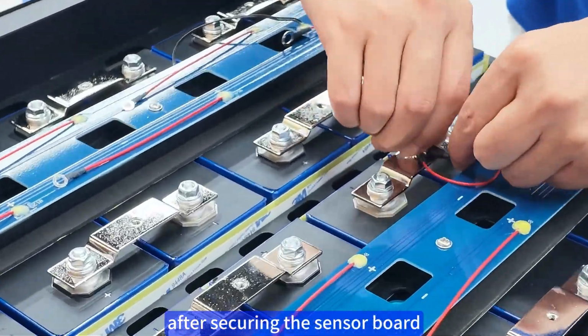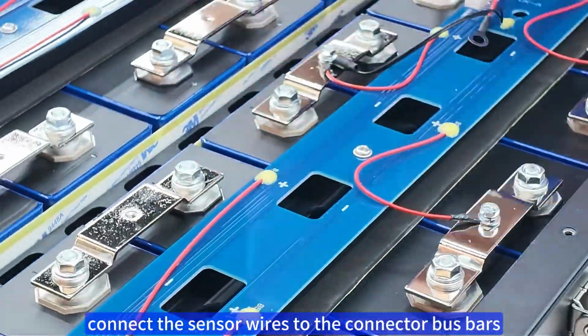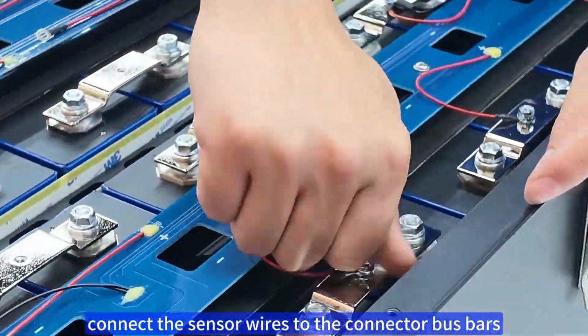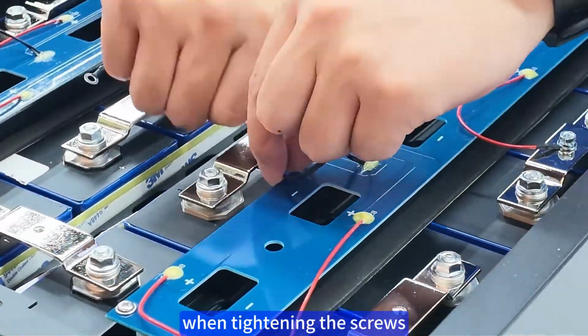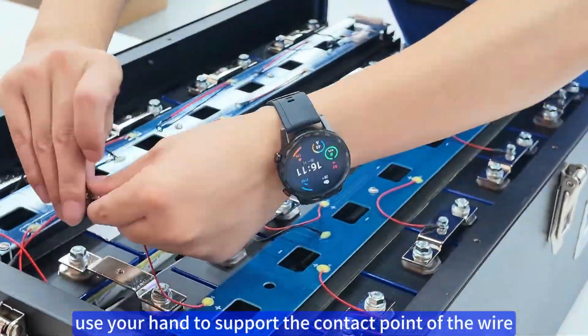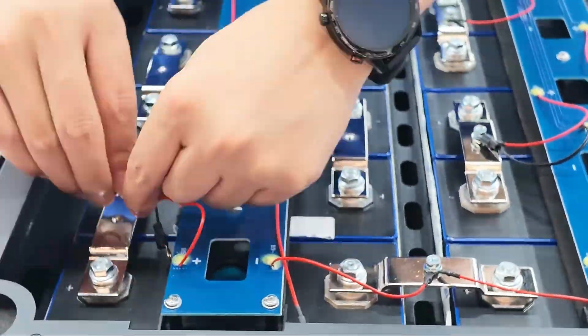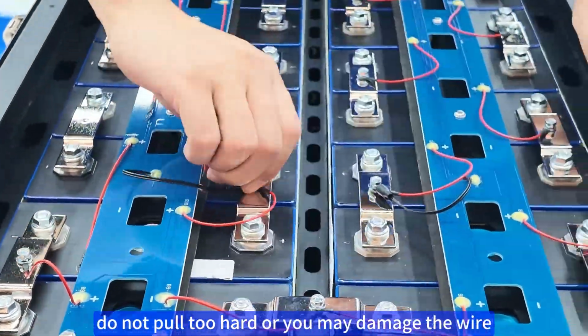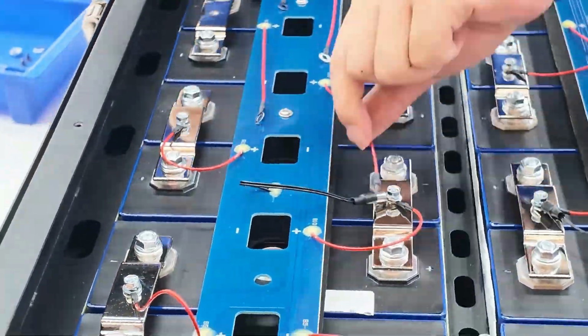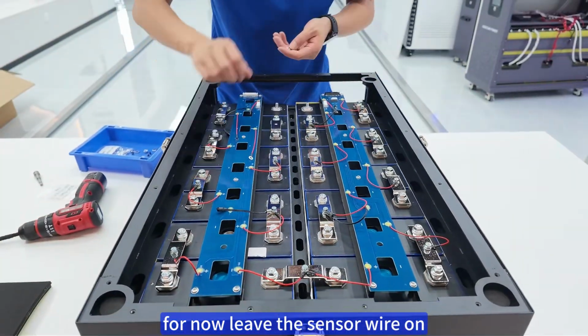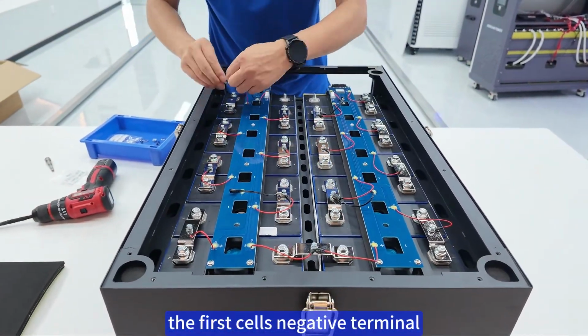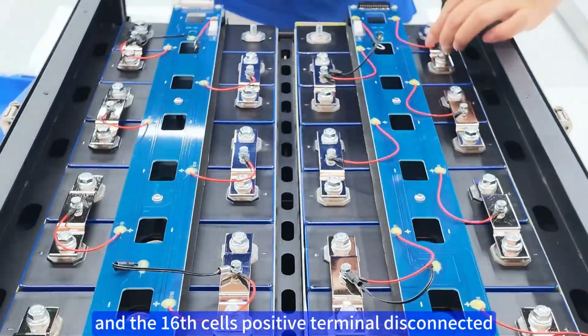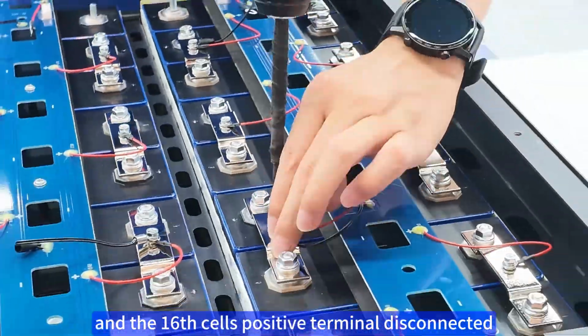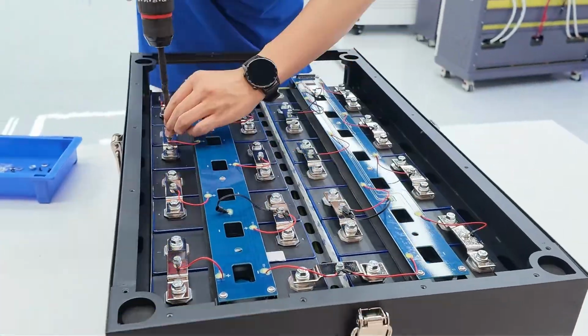After securing the sensor board, connect the sensor wires to the connector bus bars. When tightening the screws, use your hand to support the contact point of the wire. Do not pull too hard, or you may damage the wire. For now, leave the sensor wire on the first cell's negative terminal and the 16th cell's positive terminal disconnected.